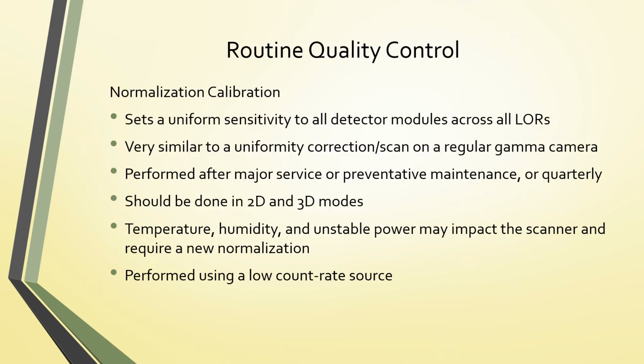The next QC is a normalization calibration. I like to describe this very similar to a uniformity correction on a regular gamma camera. It sets the uniform sensitivity to all detector modules across all lines of response. And it's performed after major service or preventative maintenance, and at the very minimum is performed quarterly. It should be done in 2D and 3D modes. The temperature, humidity, and unstable power may impact the scanner and require a new normalization.